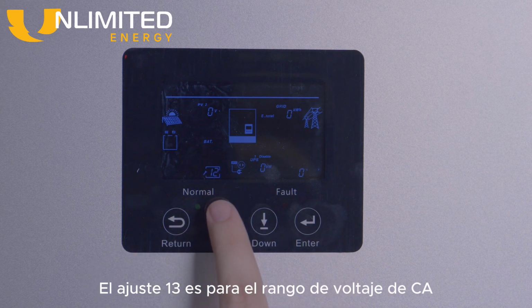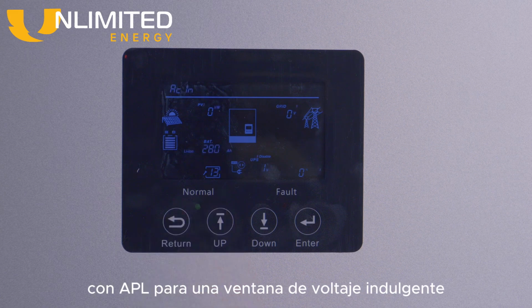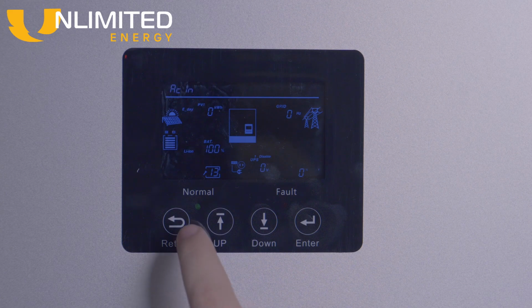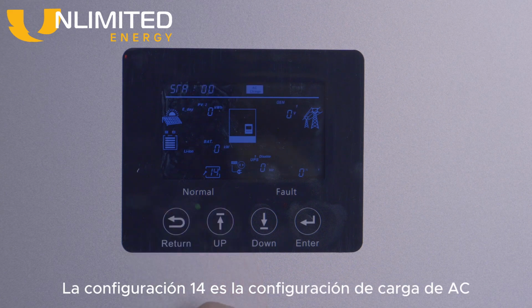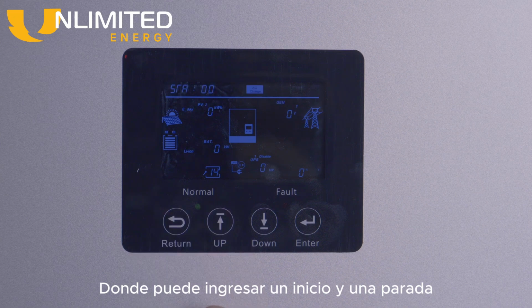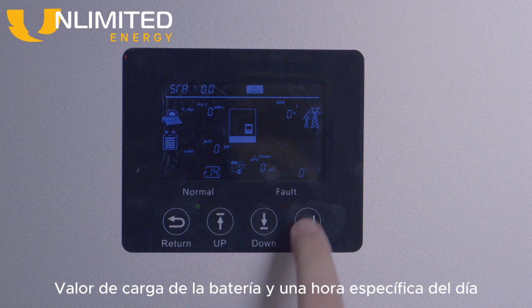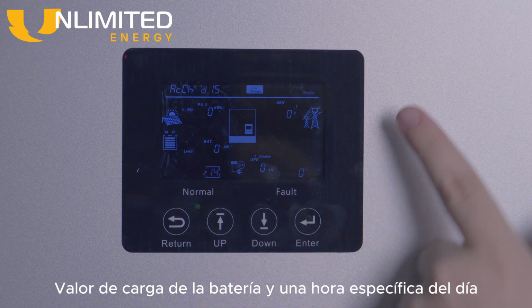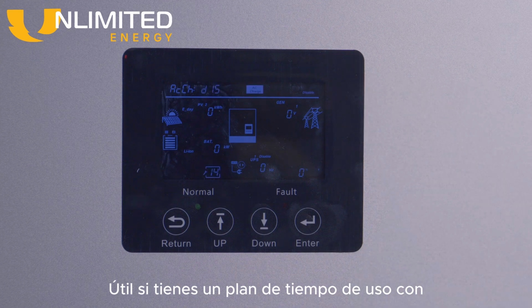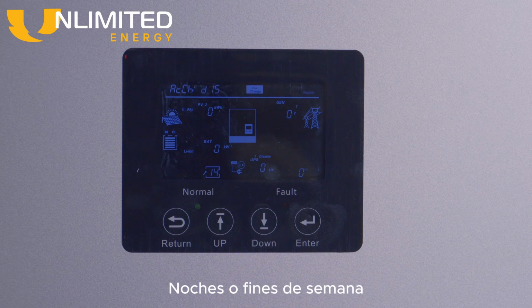Setting 13 is for AC voltage range with APL for a lenient voltage window and UPS for a tight voltage window. Setting 14 is AC charge setup, where you can input a start and stop battery charge value and a specific time of day. Useful if you have a time of use plan with free power nights or weekends.